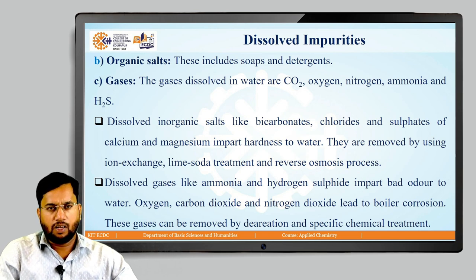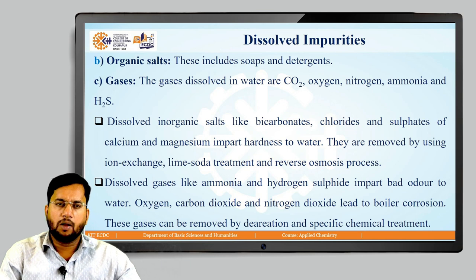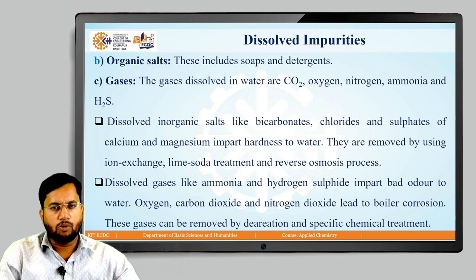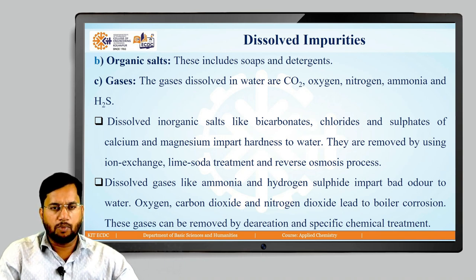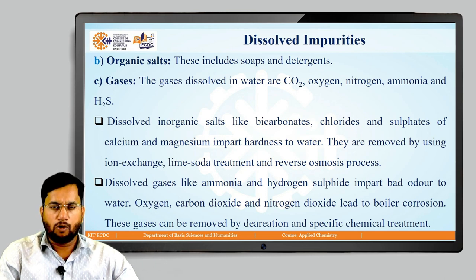However, dissolved gases like ammonia and hydrogen sulfide impart bad odour to water, whereas oxygen, carbon dioxide, and nitrogen dioxide lead to boiler corrosion, as they have strong affinity towards metal and can corrode metallic material. Dissolved gases can be removed by de-aeration and specific chemical treatment, if boiling is not suitable.